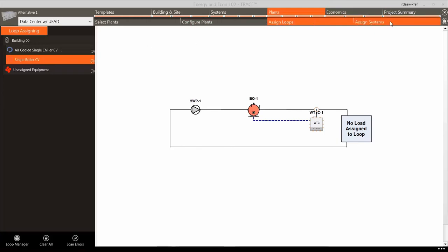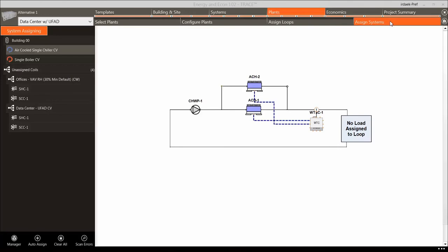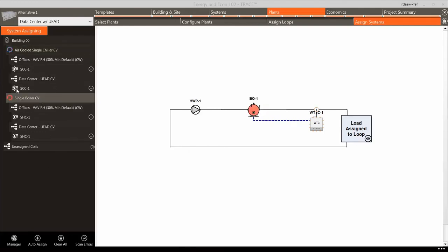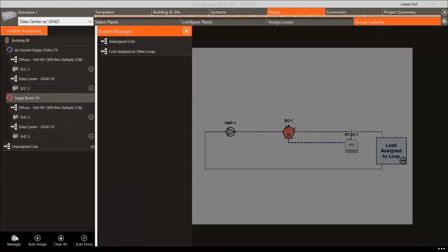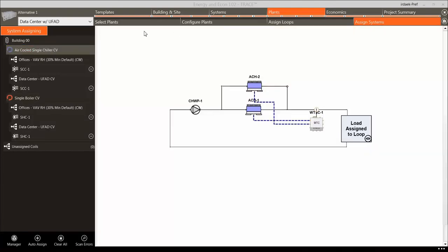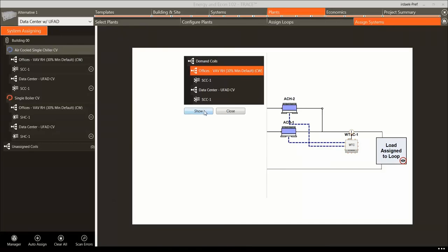We can now move on to the Assign Systems section, which allows us to assign the air-side systems and respective zone-level equipment to specific plant loops. Since we have a VAV system with zone-level reheat, we can use the Auto-Assign feature in the bottom left-hand corner. This automatically assigns all cooling coils to the cooling loop and all heating coils to the heating loop. If you had a system with dedicated outdoor air units tied to specific cooling loops, you may want to manually assign coils to different loops. Clicking on the chilled water loop will show the VAV system in the demand box.